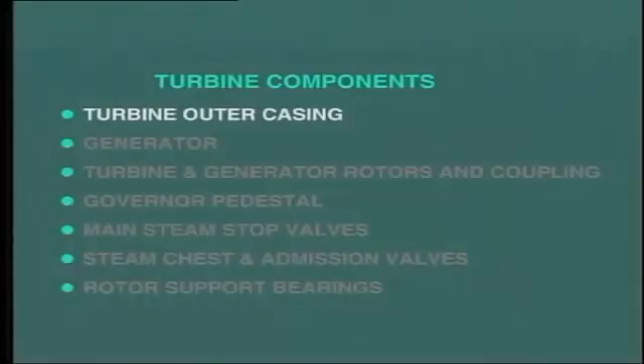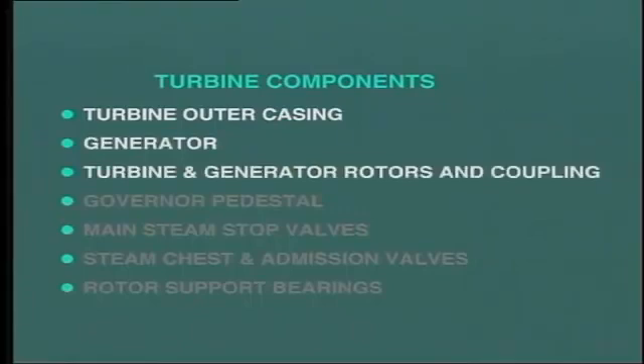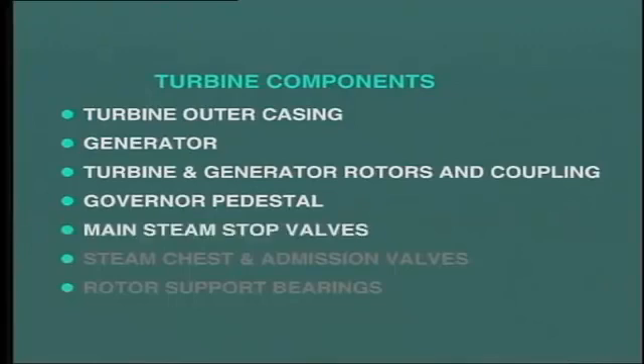Other components noticeable here are the governor pedestal, which supports the front end bearing and the governor system. Steam from the stop valve is fed into steam chests located on either side of the turbine. The turbine admission valves are located in each steam chest to control the flow of steam into the turbine. The turbine rotor is directly coupled to the generator rotor to transfer mechanical energy produced in the turbine to the generator, where it is converted into electrical energy. Make sure that you know where the following components are located on your particular turbines: the turbine outer casing, the generator, the turbine rotor, the generator rotor, the coupling, the governor pedestal, the main steam stop valves, the steam chest and associated admission or control valves, and the location of bearings which support the turbine rotor.